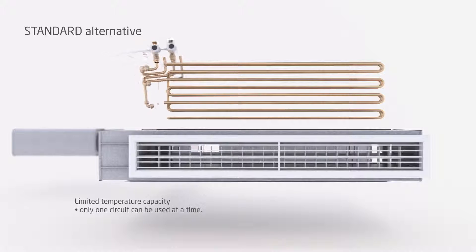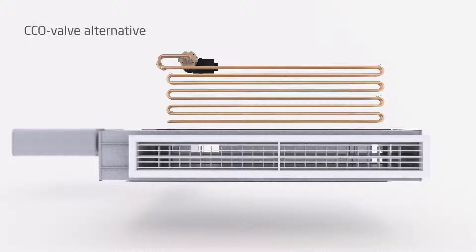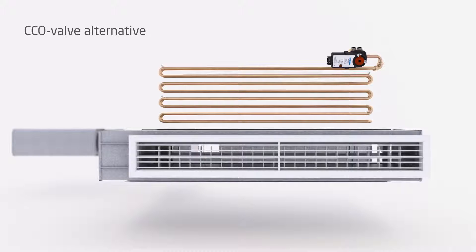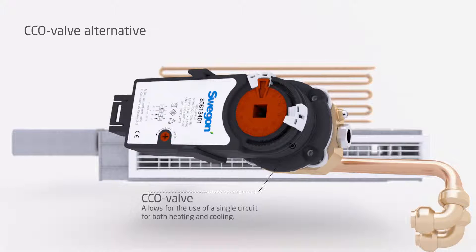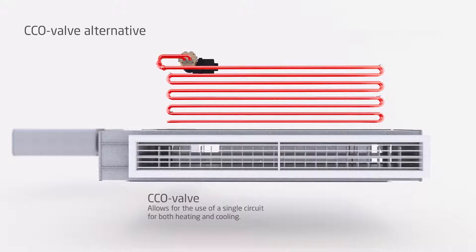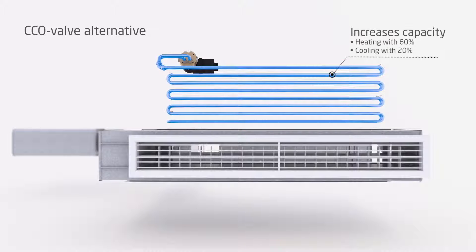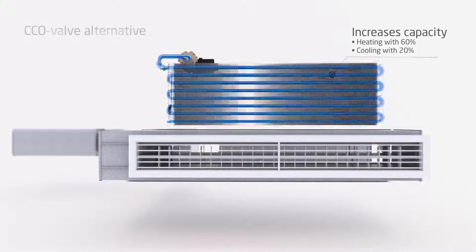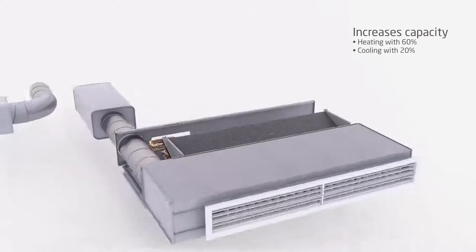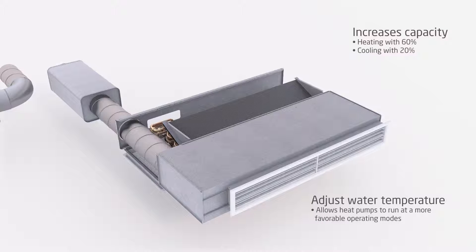To enhance the system further, the innovative Compact Changeover valve (CCO) was invented by Swegon. The CCO valve allows for the use of a single-circuit heat exchanger for both heating and cooling, meaning the entire area of the heat exchanger is utilized. This increases the heating and cooling capacity of Paragon by 60% and 20% respectively.